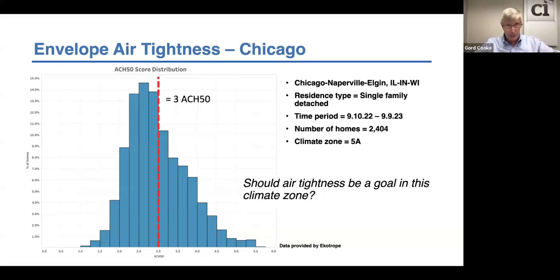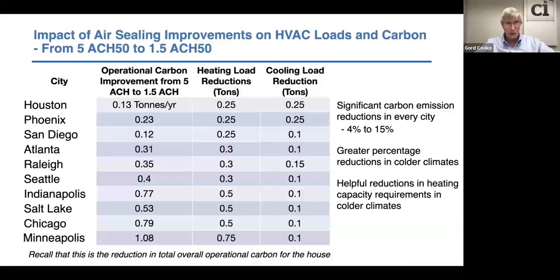And we know, again, there is a benefit if you do get tighter, as Brad was indicating. There are some other trade-offs that you can use. I thought I'd show you a pretty busy slide here, and we're near the end, but I wanted to show you the impact of air sealing improvements on HVAC loads. Start at the bottom, which is Minnesota, which is the largest in terms of heating load reductions, which is the middle column, 0.75 tons. So roughly 10,000 BTU change. So in a heating load reduction, about 10,000 BTUs.